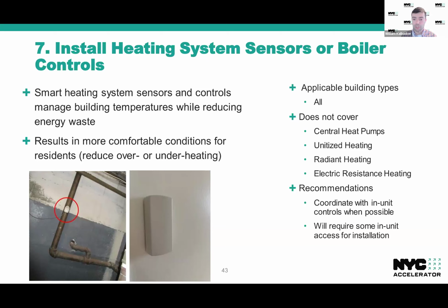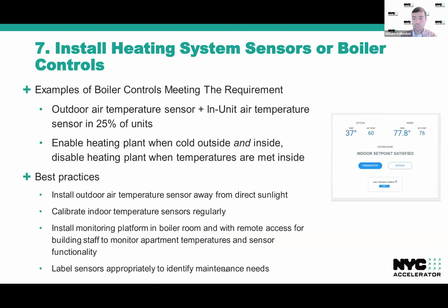You can sort of knock those all out at the same time. And again, you will need in-unit access for some of this work. So just an example of what type of control system would meet the requirements here would be a functioning outdoor air temperature sensor, basically to tell how cold it is outside, and in-unit air temperature sensors in 25% of apartments.